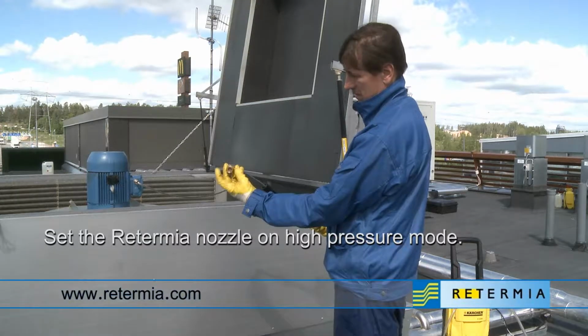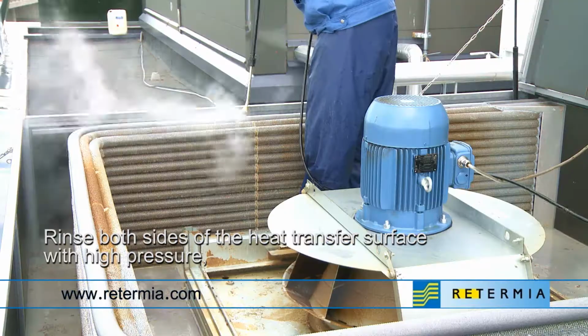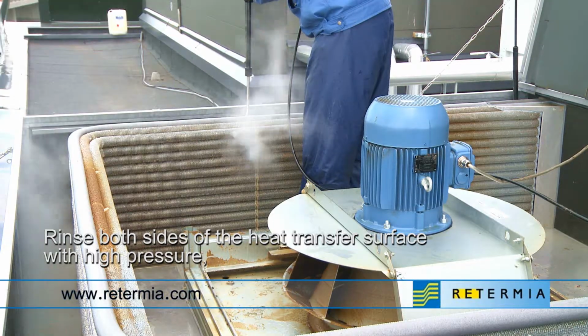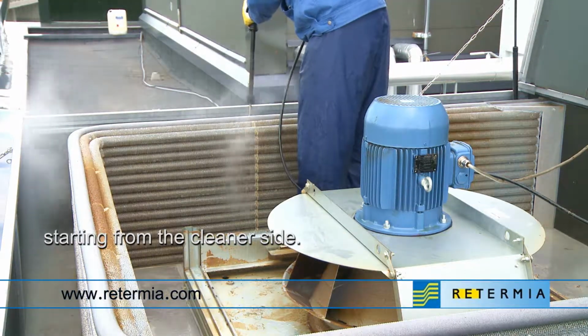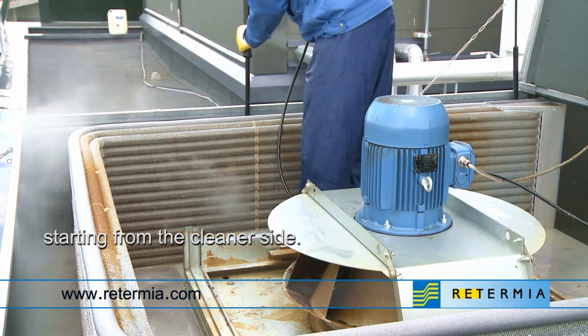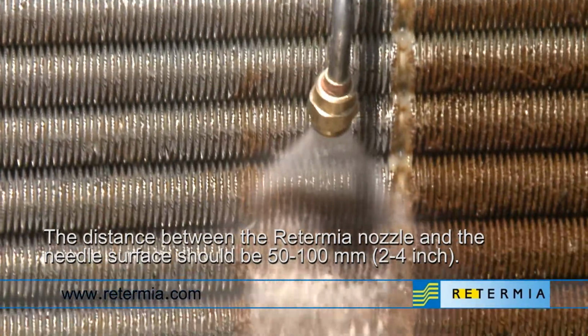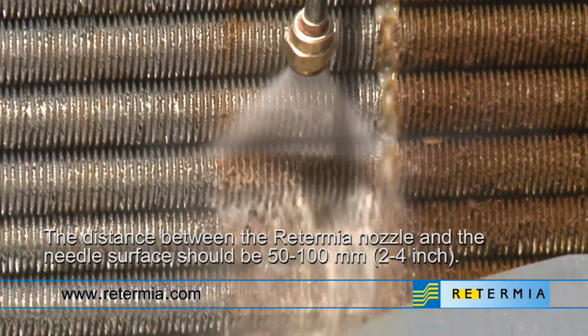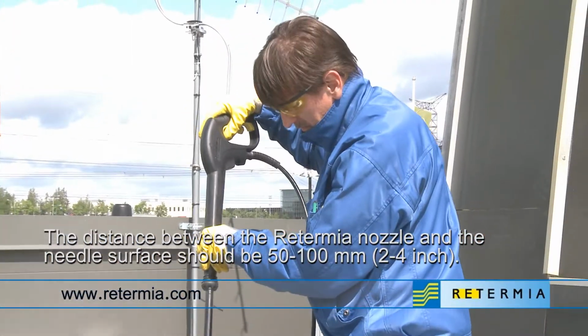Set the RETERMIA nozzle on high-pressure mode. Rinse both sides of the heat transfer surface with high pressure, starting from the cleaner side. The distance between the RETERMIA nozzle and the needle surface should be 50 to 100 mm, 2 to 4 inches.